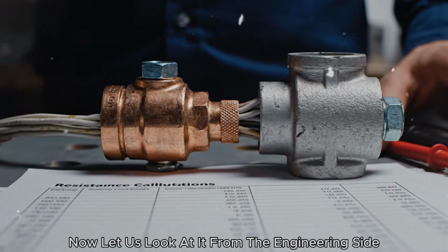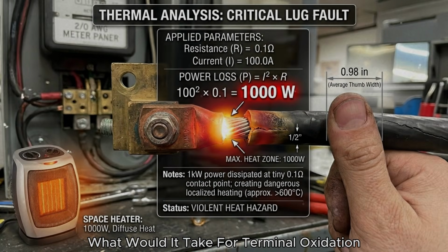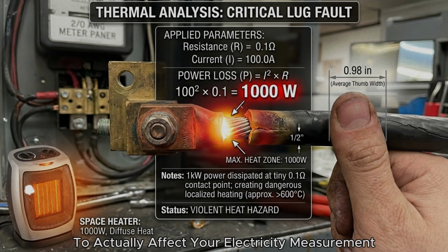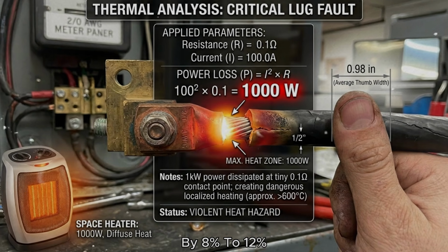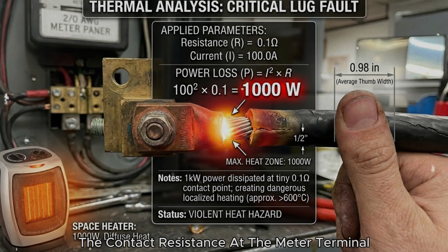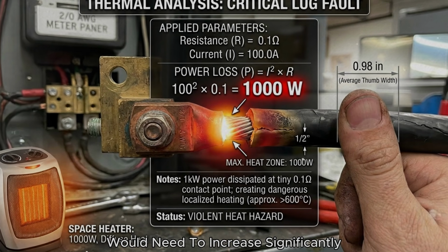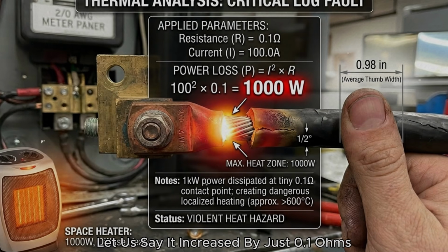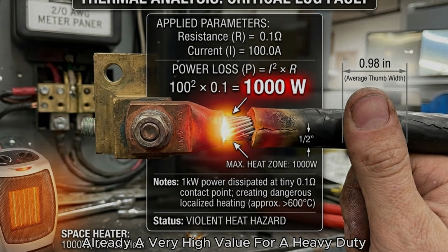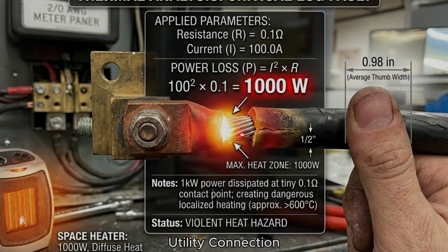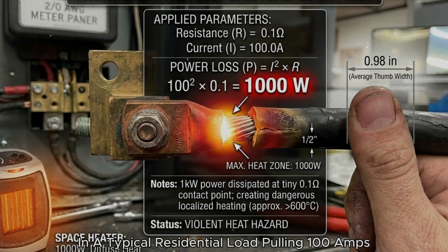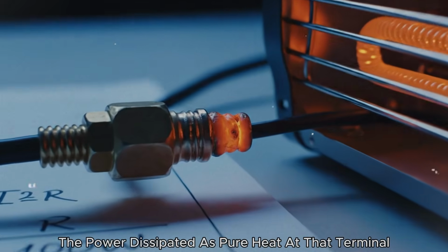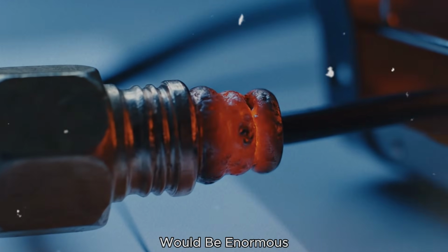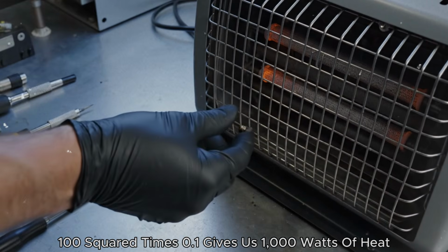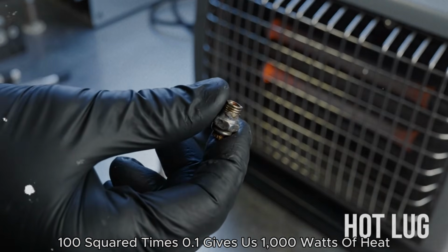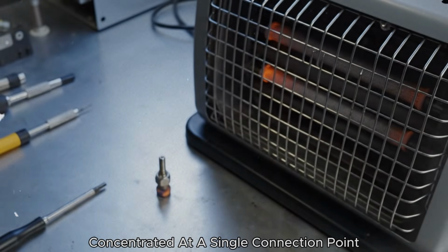Now, let us look at it from the engineering side. What would it take for terminal oxidation to actually affect your electricity measurement by 8% to 12%? The contact resistance at the meter terminal would need to increase significantly. Let us say it increased by just 0.1 ohms, already a very high value for a heavy-duty utility connection. In a typical residential load pulling 100 amps, the power dissipated as pure heat at that terminal would be enormous. 100 squared times 0.1 gives us 1,000 watts of heat concentrated at a single connection point.